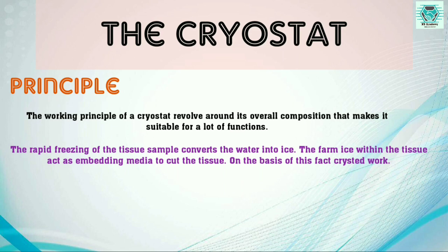The working principle of a cryostat revolves around its overall composition, which makes it suitable for a lot of functions. This kind of rapid freezing of the tissue sample converts the water into ice. The firm ice within the tissue acts as the embedding media to cut the tissue, and on this basis the cryostat actually works.